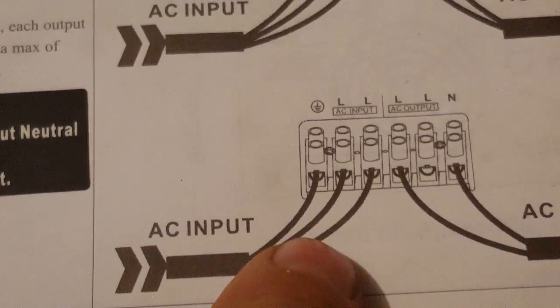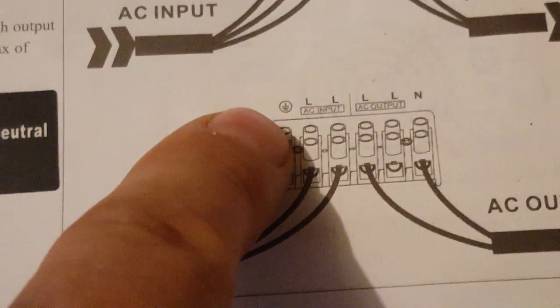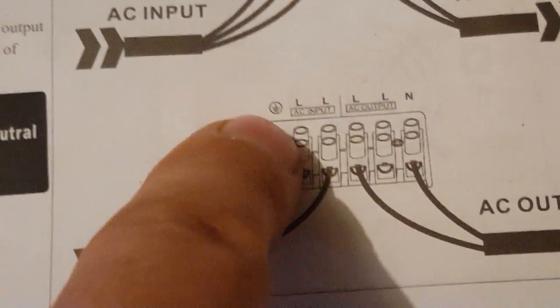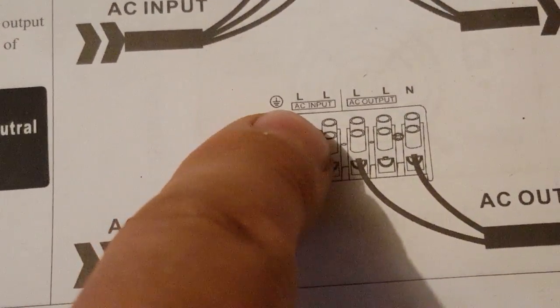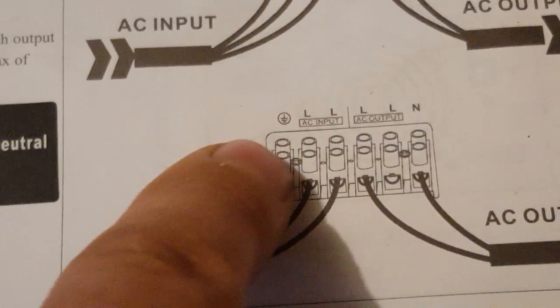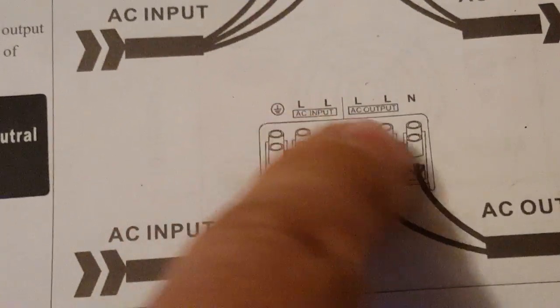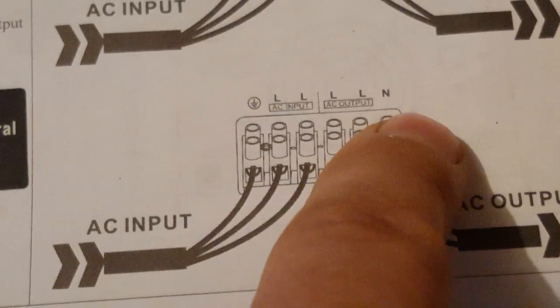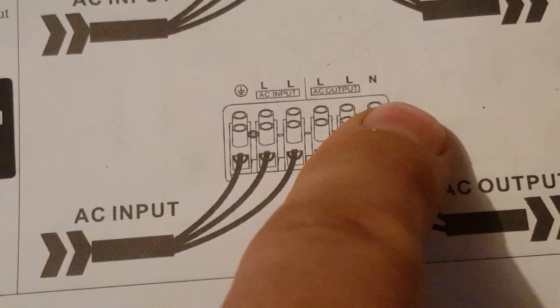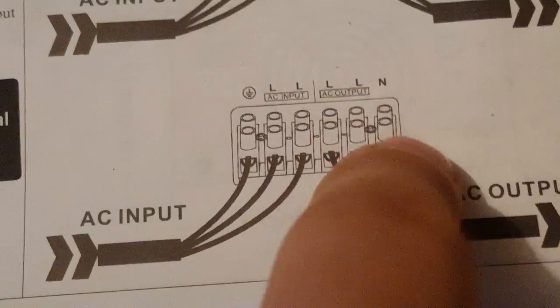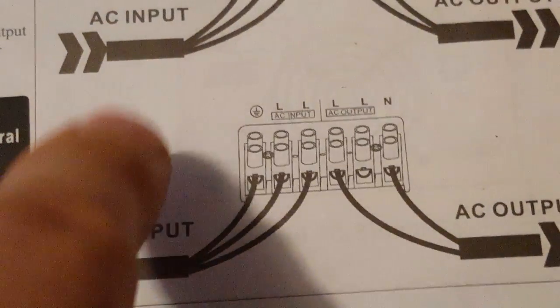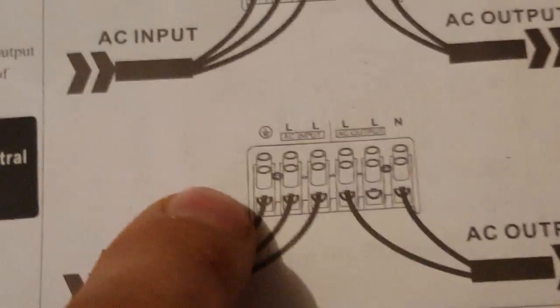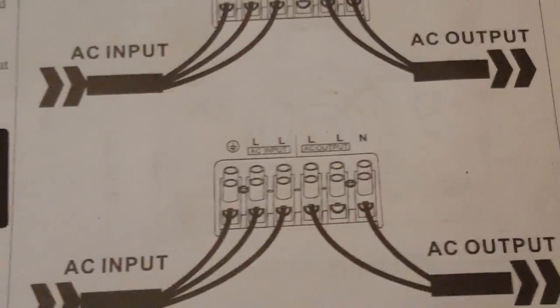So that's how you wire up this circuit. This is the AC input, that's a ground circuit. This is from the main panel, leg one, leg two comes from the main panel, and these two go to the sub panel, and attach the neutral leg to the sub panel. So my neutral leg is never connected to the ground circuit, you understand.